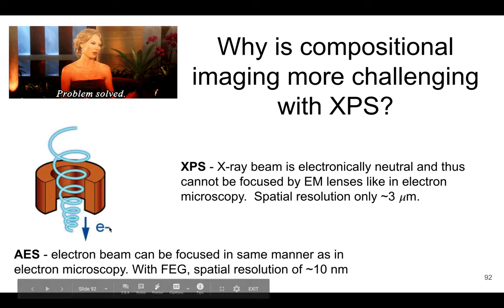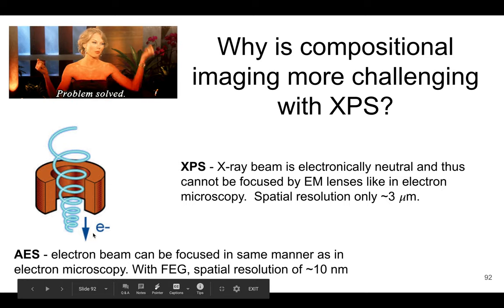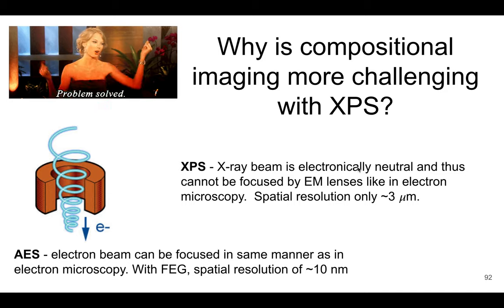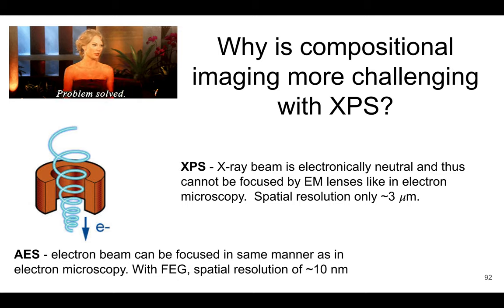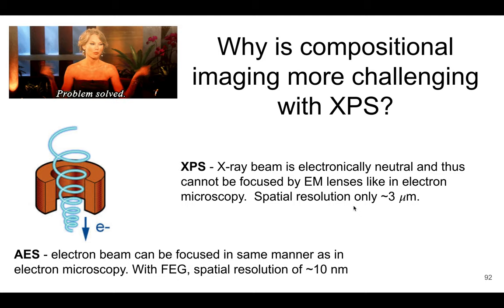Using an electron beam, we're able to focus in a similar manner to electron microscopy. With a field emission gun we can get really low spatial resolution — down to 10 nanometers — because we know how to manipulate an electron beam with lenses. However, x-rays used in XPS are electronically neutral, so those same electromagnetic lenses cannot focus x-rays the way they can with AES. Because we can't control x-rays as well to produce a very small beam, our spatial resolution is about 3 microns — compared to 10 nanometers with AES.